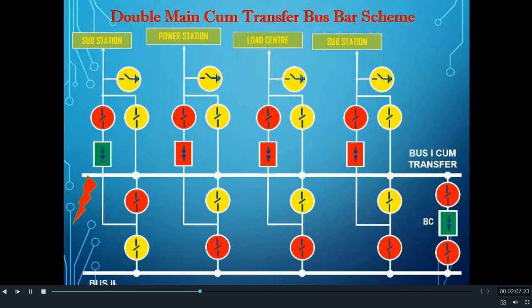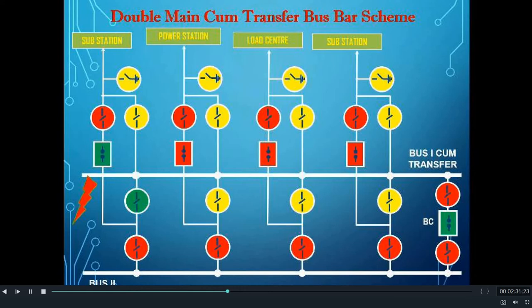To do that, first we will isolate the fault bus. We will open the bus isolator which was connecting feeder number 1 to bus 1. After opening the bus isolator, we shall close the other bus isolator which will connect feeder 1 to bus 2. When feeder number 1 gets connected to bus 2, we can again close the circuit breaker of feeder 1 and bring feeder 1 back into service by connecting all the feeders to bus 2.